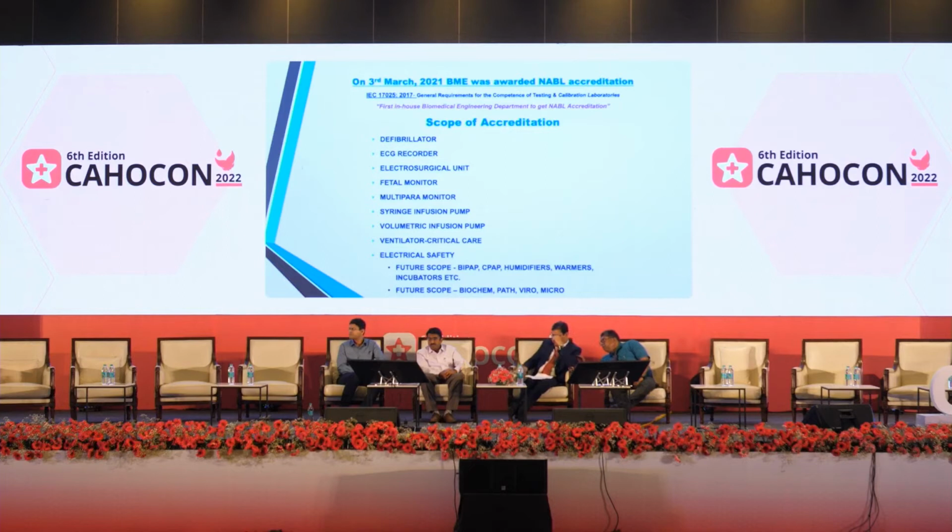In March 2021, we were awarded NABL accreditation, the first in-house biomedical engineering department to get NABL accreditation in the country. Our scope of accreditation includes defibrillators, ECG recorders, electrosurgical units, and so on. Now we are working to include more equipment in the future, like BiPAP, CPAP, humidifiers, warmers, incubators, etc. We are also planning to extend our scope to the labs, to biochemistry, pathology, and virology in the near future.